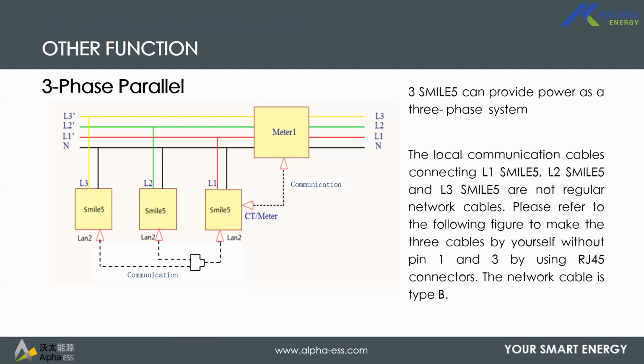As I have said earlier, the systems can be connected in parallel. For a three-phase scenario, you are limited to one inverter per phase. That is, you'll basically have a 15 kilowatt three-phase system with peak power on each phase being 5 kilowatt. Your neutral is common in a three-phase scenario, so it's wired to all inverters, and each phase to each inverter. You only need one meter, which is a three-phase meter, wired to your first inverter, which is your master inverter. Then from that inverter, you daisy chain from inverter 1 to inverter 2 and 3.